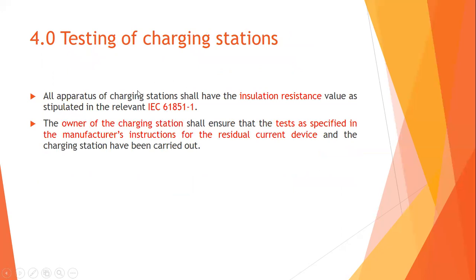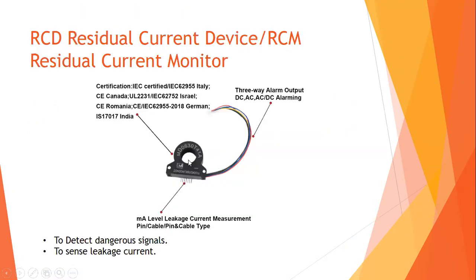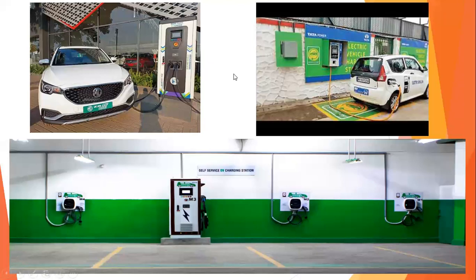Rule 4 covers testing of charging stations. All apparatus of charging stations shall have insulation resistance values as stipulated in IEC 61851. The owner of the charging station shall ensure that tests specified in the manufacturer's instructions for the residual current devices are carried out. For example, Tata Power has installed charging stations and creates SOPs for the owner on how it should be tested daily or on a periodic basis.